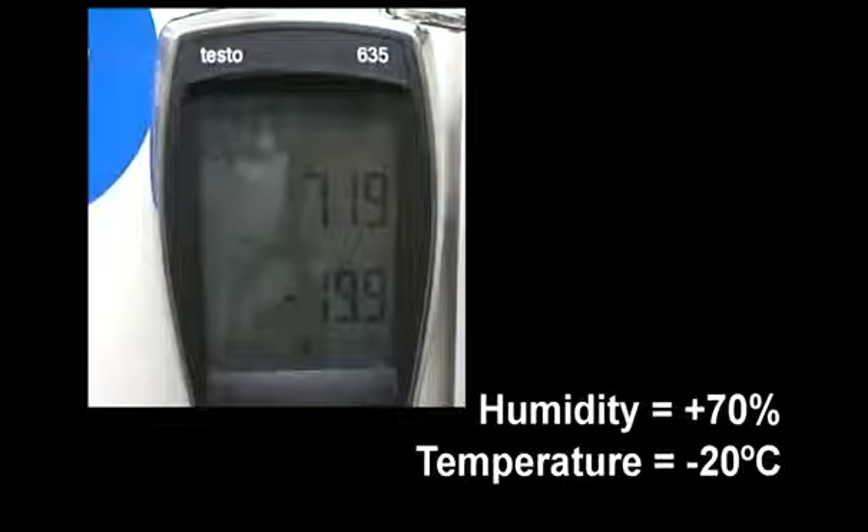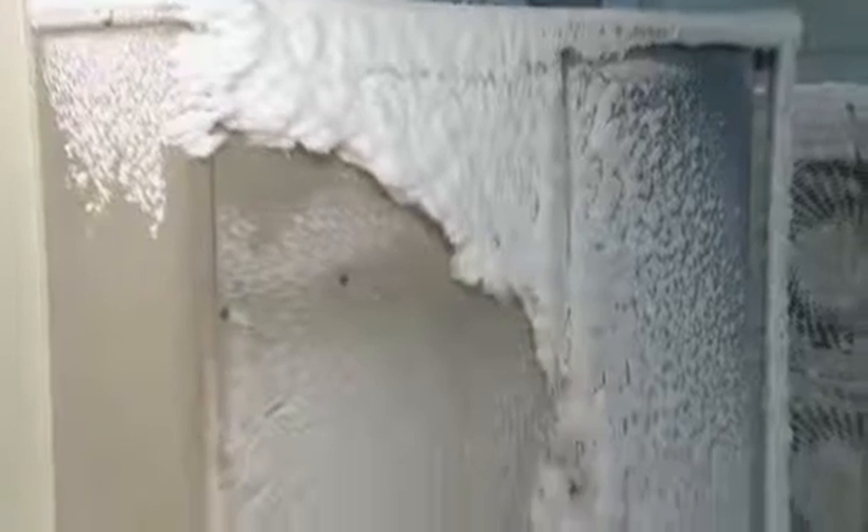It withstands a power cut of three hours in extreme conditions of minus 20 degrees Celsius and a humidity of 70%. By adding an external fan to the test room setup, our technicians were even able to simulate wind blowing at a velocity of three meters per second. We monitored the temperature in the water piping during the entire test to check that it remained above two degrees Celsius.